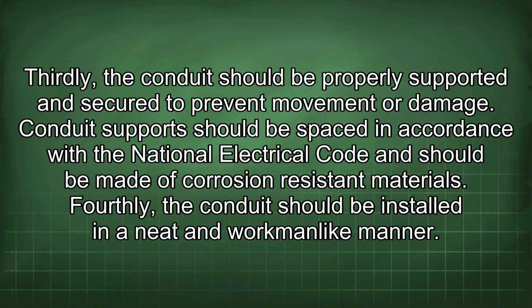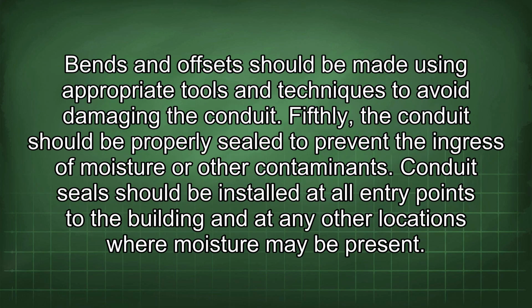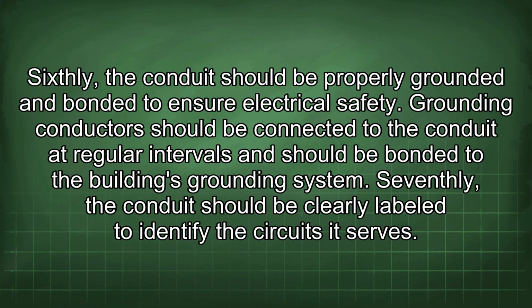Conduit support should be spaced in accordance with the National Electrical Code and should be made of corrosion-resistant materials. Fourthly, the conduit should be installed in a neat and workmanlike manner. Bends and offsets should be made using appropriate tools and techniques to avoid damaging the conduit. Fifthly, the conduit should be properly sealed to prevent the ingress of moisture or other contaminants. Conduit seals should be installed at all entry points to the building and at any other locations where moisture may be present. Sixthly, the conduit should be properly grounded and bonded to ensure electrical safety. Grounding conductors should be connected to the conduit at regular intervals and should be bonded to the building's grounding system.